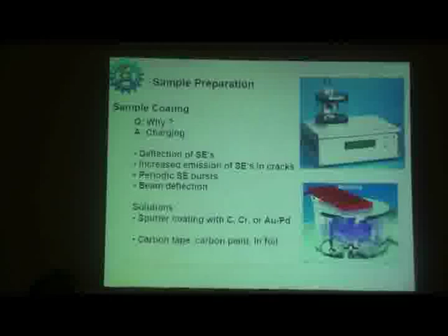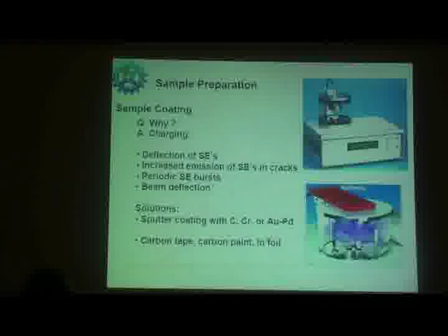Sometimes your sample may not be conducting, because mostly the electron beam interaction takes place. The electrons are highly charged particles. When your material is non-conducting, like ceramic or any biological sample, the electrons will fall on the sample, get charged and get heated. To avoid that, you have to give a small coating like carbon or chromium or gold. Normally we do it with sputtering. This will be at the nanometer level, which will not hide the information you are looking for. So a gold or any other conductive coating is required when your sample is non-conducting, for seeing in the cell.